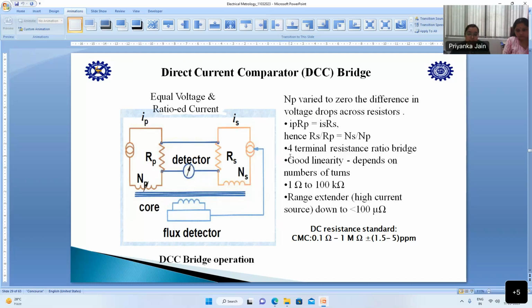Usually we use a 4-terminal resistance ratio bridge for good linearity. Up to 100 kilo ohm, we have 4-terminal resistance. Beyond 100 kilo ohm, from 1 mega ohm to 1 giga ohm, we have 2-terminal, and beyond that, we have N-type connectors. So this particular DCC bridge is capable of measuring 1 ohm to 1 giga ohm on the higher side, and on the lower side, it is 10 micro ohm to 0.1 ohm. The lower side works on high current, from 1 amp to 600 amps.